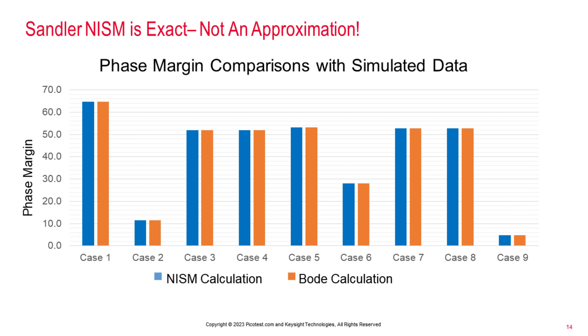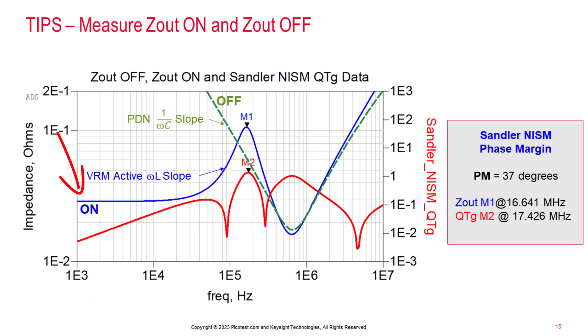A similar comparison between measured Bode plots and NISM measurements yielded consistent results well within one degree. The most important tip for using the Sandler NISM stability assessment is to find the correct impedance peak and QTG peak. This is done by comparing the control loop powered-on and powered-off impedances.